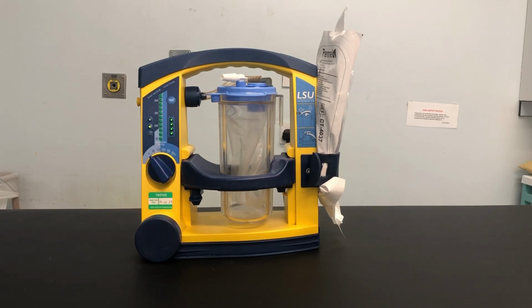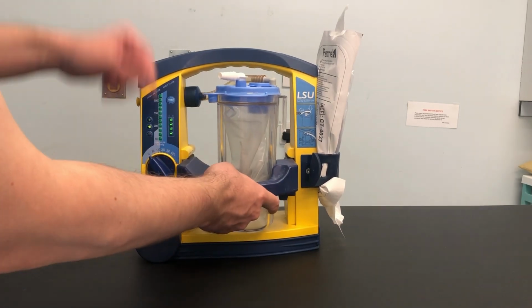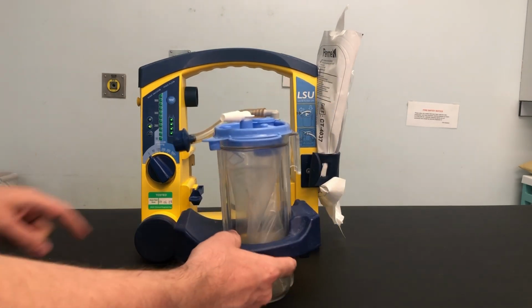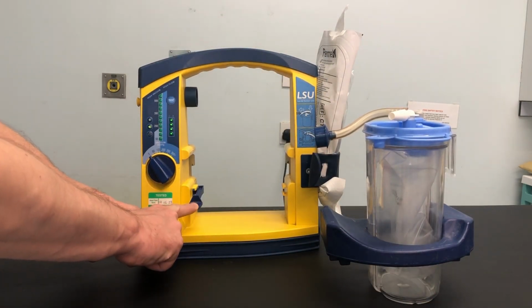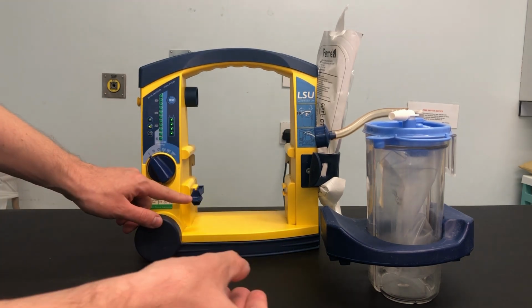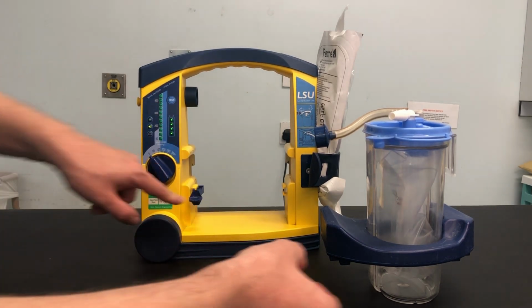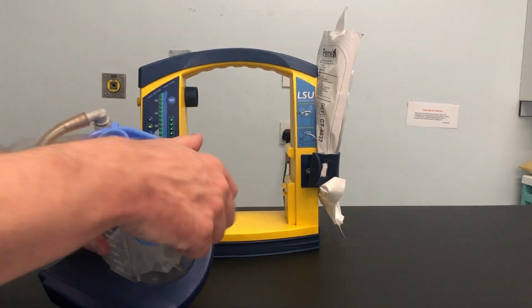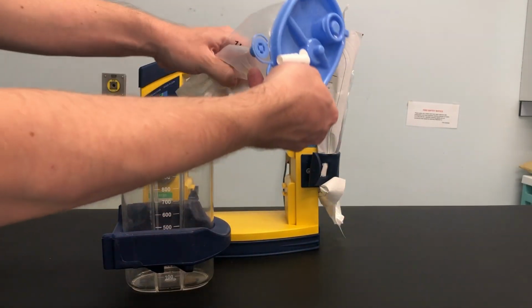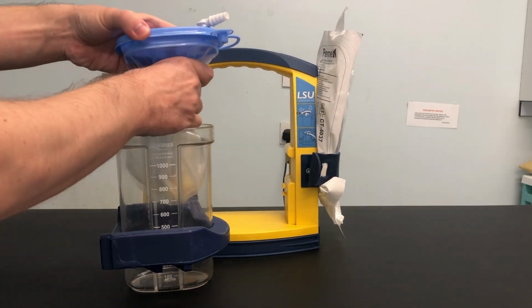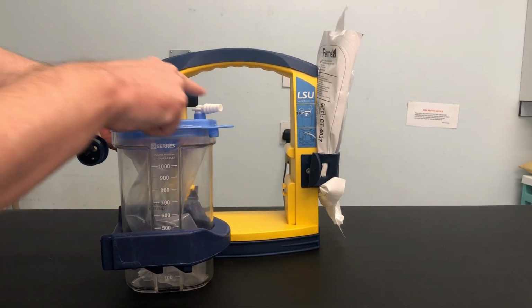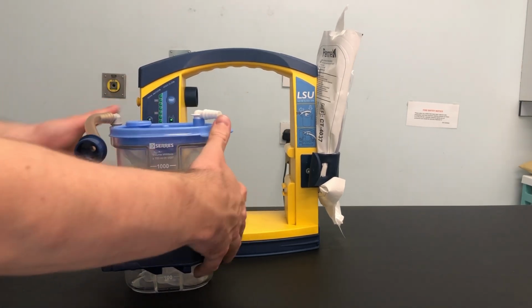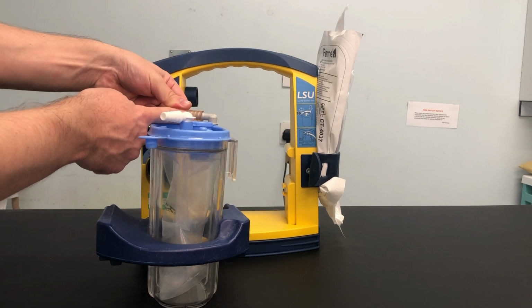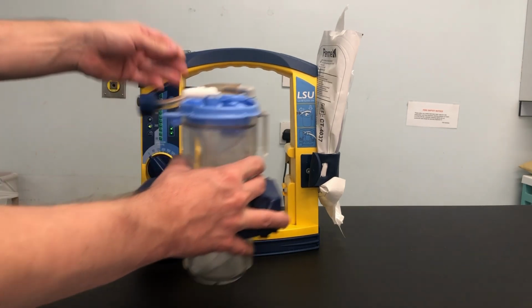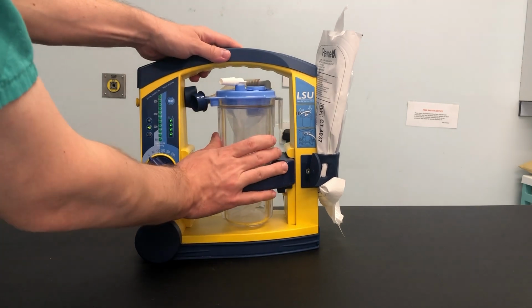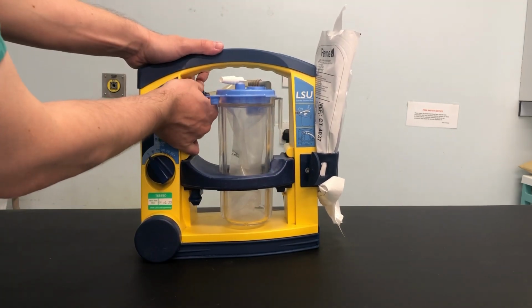So, initially you remove the canister and disconnect the vacuum tubing from the device. To release the canister from the blue canister holder, press down on the release arm and slide the holder out of the device. Put the disposable liner into the canister. Ensure that the white angle connector, patient inlet, is situated on the top of the blue liner lid to connect the suction tubing. Connect the vacuum tubing to the grey connector, ensuring it is properly connected to the LSU and to the canister. Insert the canister into the blue canister holder and slide it into the LSU unit.